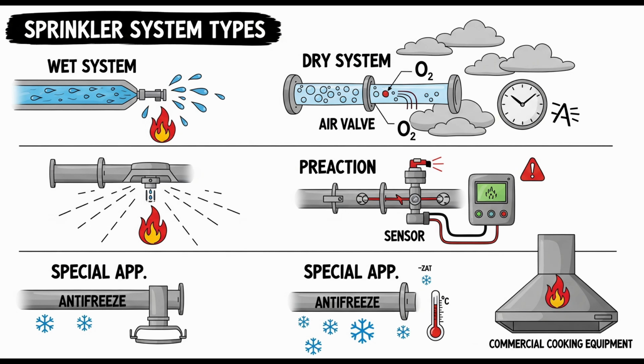Right there, immediately inside the cold space, the standard requires a section of pipe to be installed that is specifically arranged for removal. Arranged for removal, like a spool piece or union connection. How long does this section need to be? It has to be a minimum 30 inches long. The reason for this removable section is simple but absolutely vital. It's there purely to facilitate inspection and, if necessary, the easy removal of ice plugs if they happen to form right at or near that critical transition point from the warm area to the cold area. Why is that point so critical for ice plugs? Because even with dry air supplies and careful installation, some moisture might still condense or freeze right at the point where the relatively warm pipe first enters the deeply cold freezer environment.